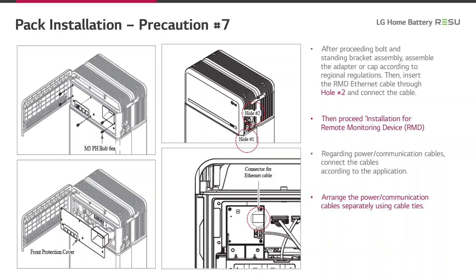This slide refers to the finalization of the connection of the battery control unit with the battery modules. After proceeding with bolt and standing bracket assembly, assemble the adapter or cap according to regional regulations. Then insert the RMD Ethernet cable through hole number two and connect the cable, then proceed with the chapter on installation for the remote monitoring device. Regarding the power communication cables, connect the cables according to the application and arrange the power communication cables separately using cable ties.